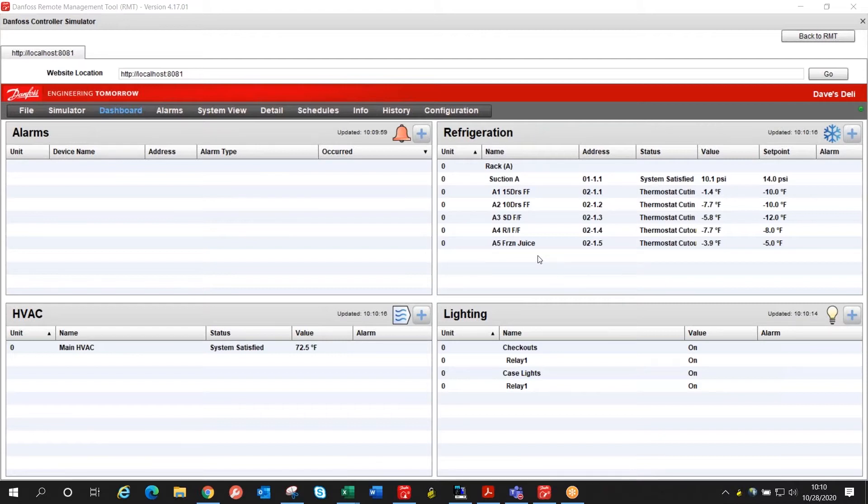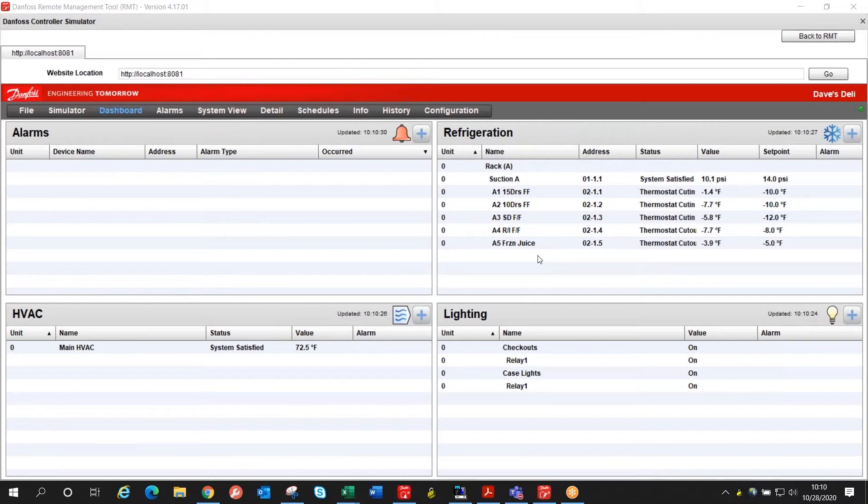So I've already set up in the compressor relay a dummy relay to serve as the relay for the compressor so we can see when it's actually turning on and off and then we'll use a calculation to force it to run once a day for 10 minutes.